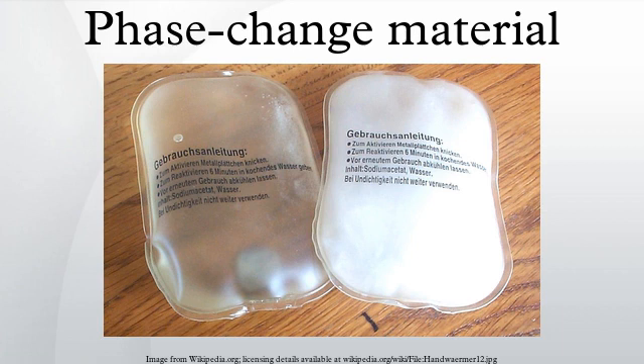Technology development and encapsulation: the most commonly used PCMs are salt hydrates, fatty acids and esters, and various paraffins. Recently, ionic liquids were also investigated as novel PCMs. As most organic solutions are water-free, they can be exposed to air, but all salt-based PCM solutions must be encapsulated to prevent water evaporation or uptake. Both types offer certain advantages and disadvantages. They have been used since the late 19th century as a medium for thermal storage applications, in such diverse applications as refrigerated transportation for rail and road, and their physical properties are therefore well known.